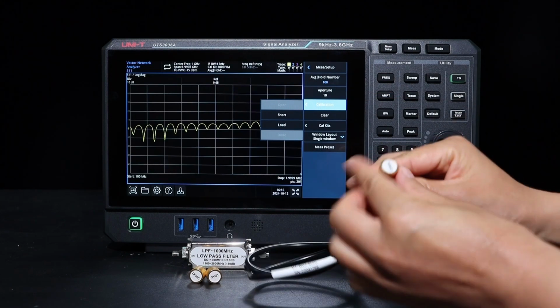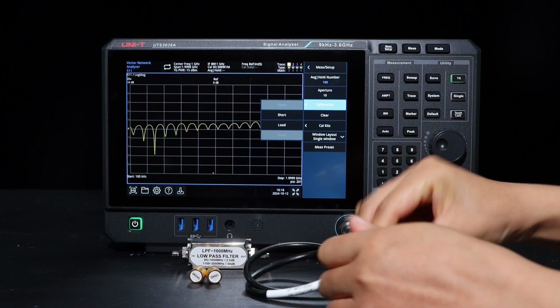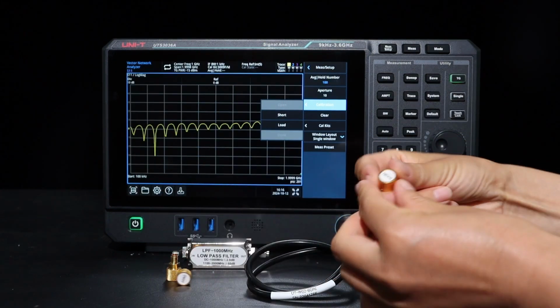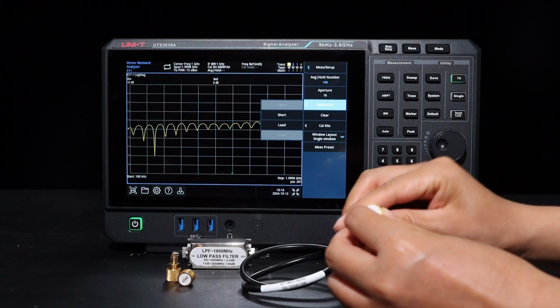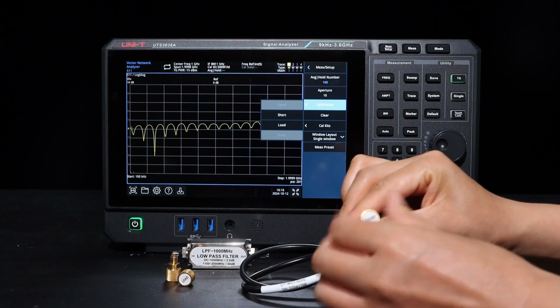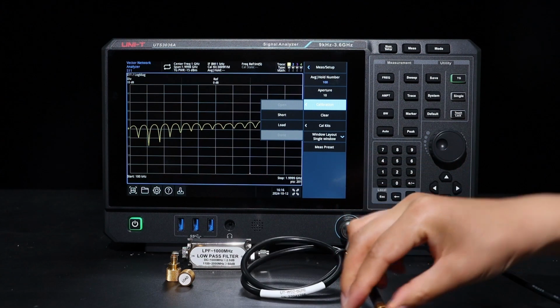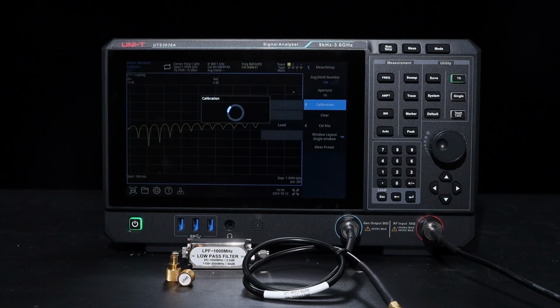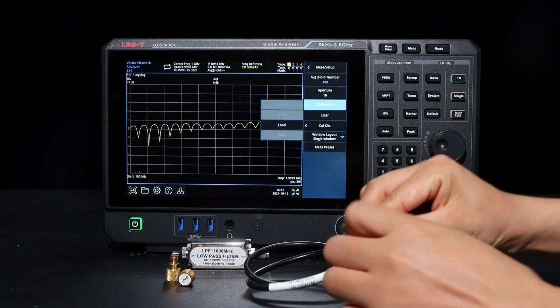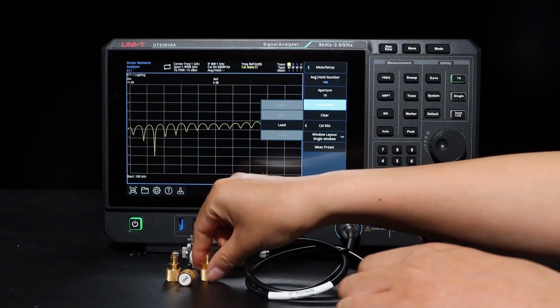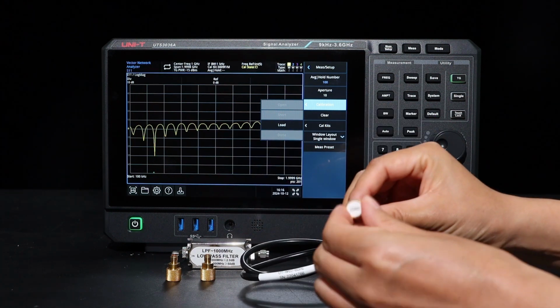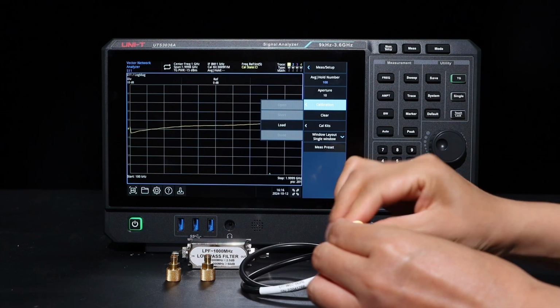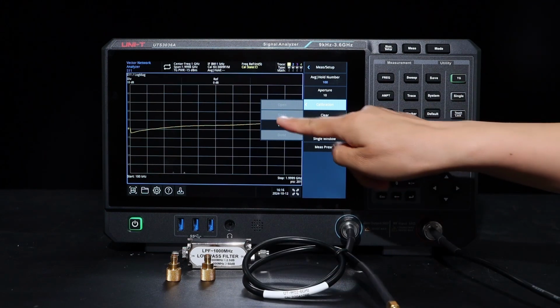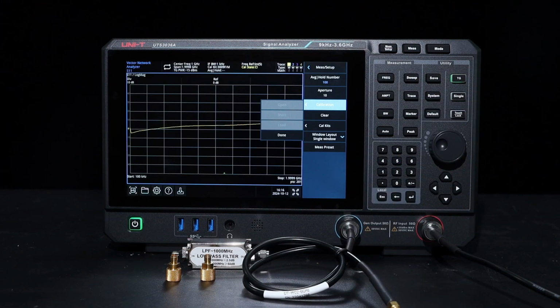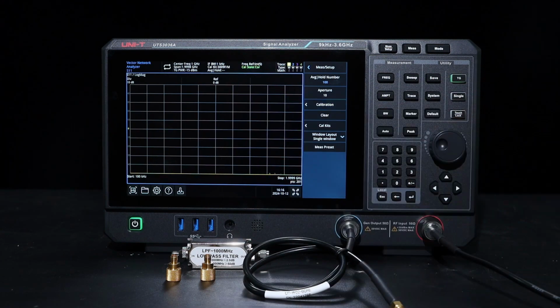After calibration, connect the short circuit calibration kit to the output port of the VNA. Then click Short. After calibration, connect the load calibration kit to the output port of the VNA. Then click Load. After the calibration is complete, the S11 is a 0 dB straight line.